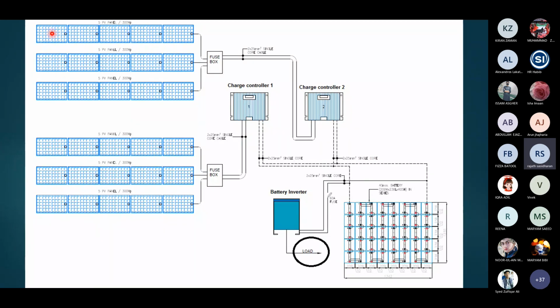Now you see here we have 5 panels, and there are multiple of these 5 panel series coming into one charge controller, with just one output. So what happens is probably this is like 800 volts, 500 volts, but the battery doesn't need that much voltage because your battery bank voltage is just 48 or 24 or whatever it is. So when you're reducing the voltage, of course the amperage increases. It's just a thumb rule calculation.